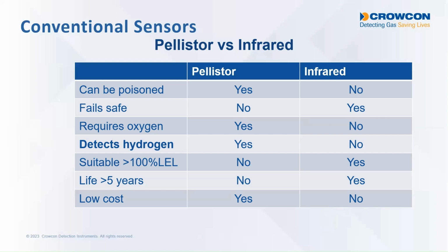And this is not just silicon, it also is leaded compounds, chlorinated compounds, fluorinated compounds. There's lots of different compounds that will have the same effect on the pellistor. It remains operational electrically, so current still passes through the bead. So the instrument still thinks the pellistor is working fine. You don't get a fault on the instrument, it just doesn't respond to gas. So this is what we call in our industry an unsafe failure, which is very undesirable. You don't know that your sensor is not responsive.